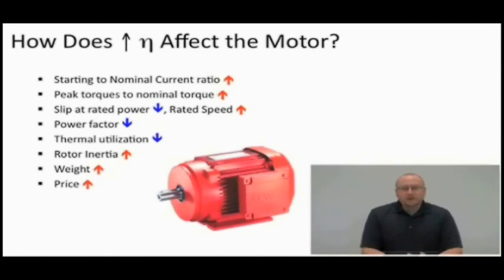But remember, back in the first section we were talking about the relative potential difference we can make in changing components and saving energy. By using a high efficiency motor, I told you it was something like 10%. Using a VFD, we could gain 30%. Changing mechanics, we could gain 60%. Well, if by using an induction motor of a higher efficiency or a premium efficiency I can only save 10% of the overall energy of my system, is it worth it? Is it worth doing that?